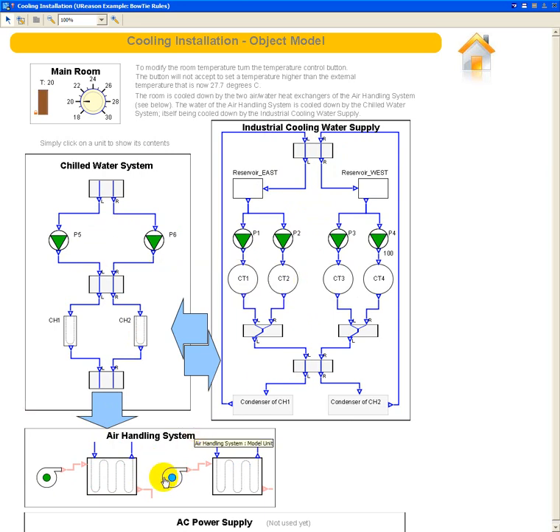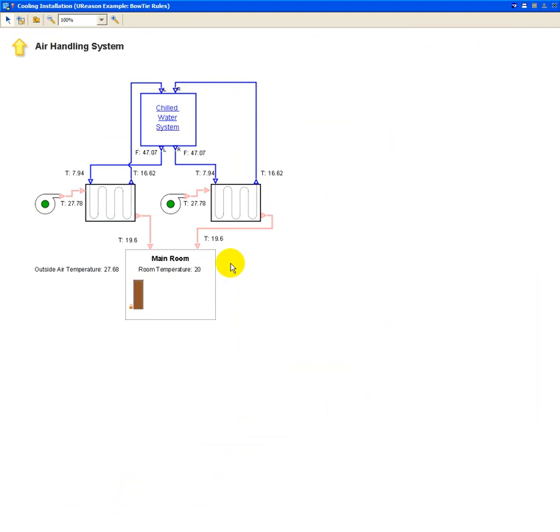Each of these units can be clicked, so I can click on the air handling system and go inside this unit and see that it consists of, in this case, two fans, as I said, blowing air into these heat exchangers. So you can see the input temperature, 27.78 degrees, being cooled down to almost 20 degrees here, and going inside this room where the actual temperature is exactly 20 degrees. And this water is coming from the chilled water system, where it comes out at almost 8 degrees and goes back into that chilled water system at almost, in this case, 17 degrees.